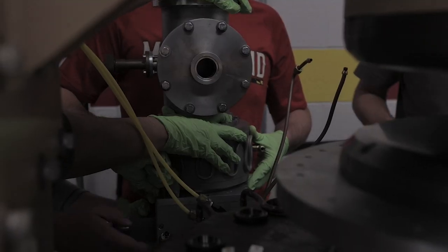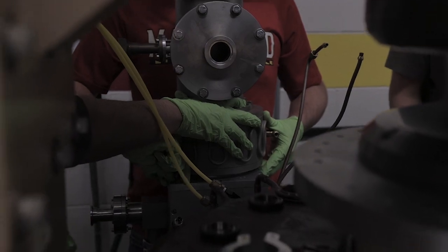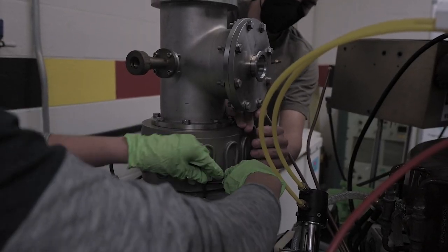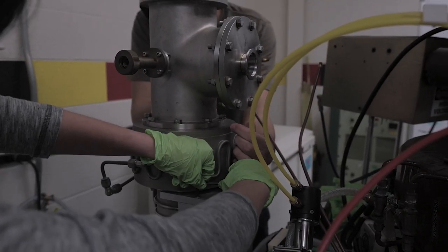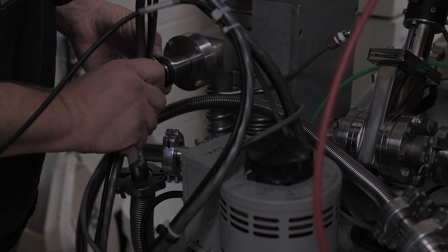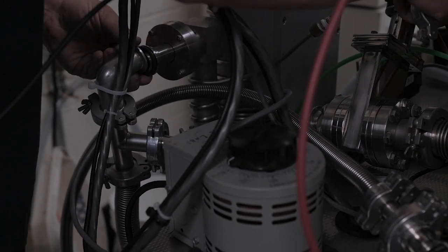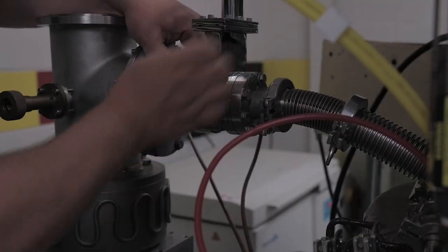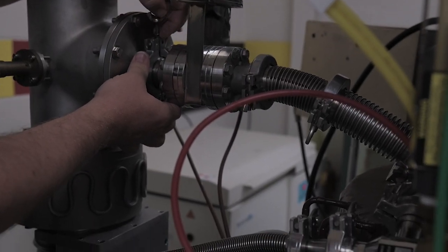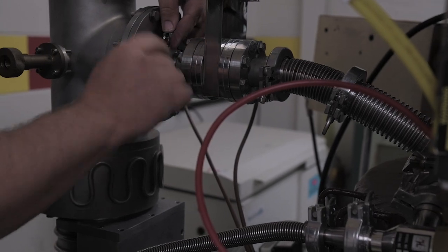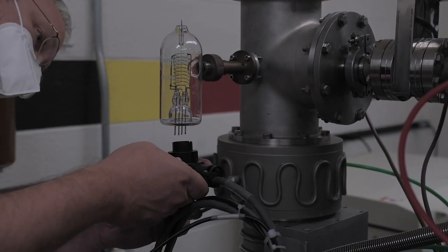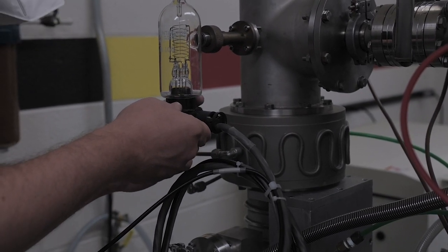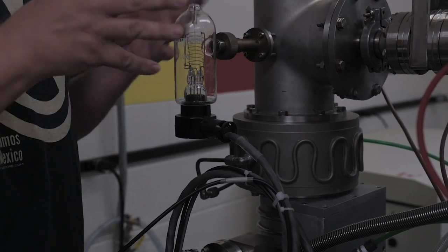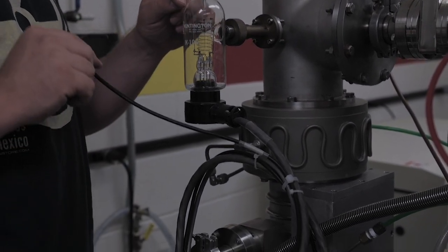The whole system is then carefully reinstalled on the 12-inch cyclotron, the roughing line is reconnected, the connection to the 12-inch chamber is made, the water cooling lines are attached to the cyclotron, and the glass Bayard-Alpert gauge is finally carefully reinstalled, having been protected the entire time to prevent any damage.